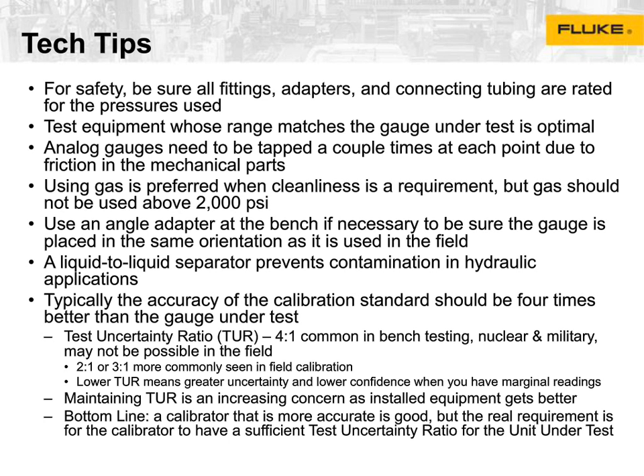If you are going to take a gauge out of the field, make sure when you calibrate it at the bench, that it's at the same orientation as it will be in the field. This is especially true for mechanical gauges, but it's also true for digital gauges. Placing it at the right orientation will help make sure that you are reducing as many error factors as you possibly can. We talk a little bit about liquid separators. That's very true in hydraulic applications, depending on what your process fluid is. If it has very high accuracy requirements, it has very high purity requirements, a liquid-to-liquid separator will really help. Most manufacturers will sell liquid-to-liquid separators to keep stuff out.